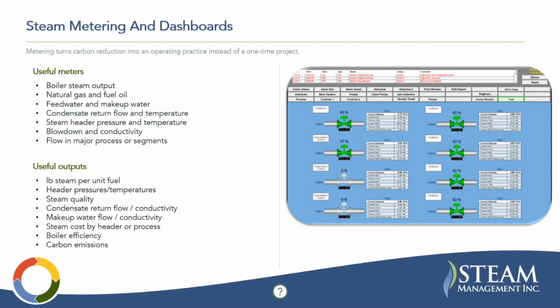Steam metering and dashboards. I won't read all these, but there's some notable data points and output metrics here. But metering gives the steam system visibility. You don't need to meter every line, but you do need enough data to understand how much steam you're making, how much fuel and makeup water it takes, where the steam is going, and how much condensate is coming back.